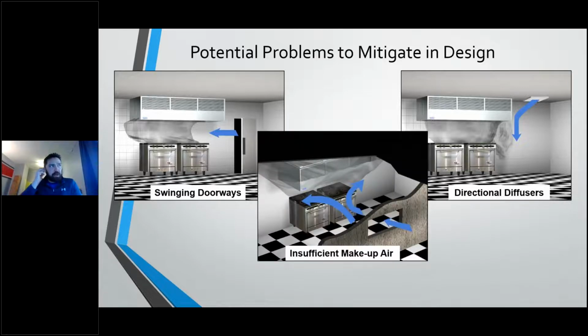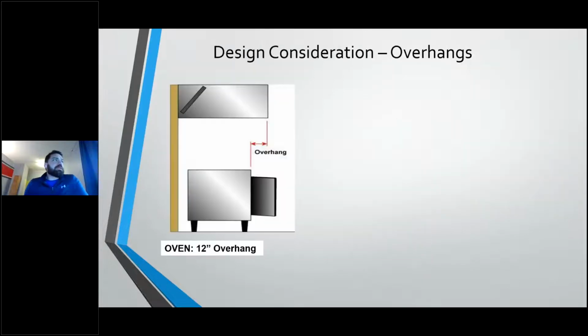The final issue or potential problem to mitigate is just insufficient makeup air. Now, in a lot of these engineered kitchen ventilation systems, we have some engineers that are expert in transfer air and HVAC and building pressure. So I don't see this one quite as often because that transfer air is accounted for. But if there isn't enough transfer air, if there's insufficient makeup air, you run the risk of starving that exhaust fan and not having capture happen. So those are really the only things to look out for when it comes to potential problems in your kitchen ventilation system. Really, it's where are there cross drafts that are possibly running underneath this hood? A cross draft in a kitchen ventilation system will kill you.